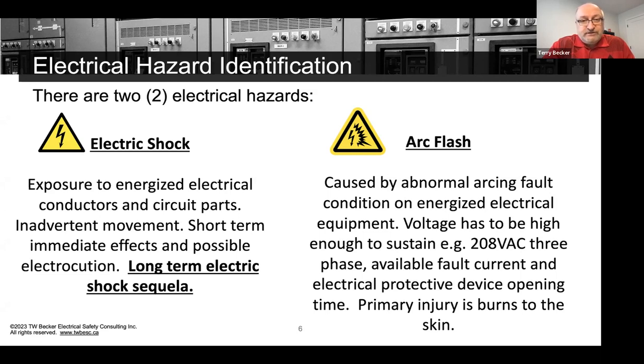The arc flash hazard, lots of stuff out there on arc flash, and I'm telling you, it continues to evolve in its growing personality. So I'm going to try and make some comments today to distill some of the misinterpretation of when a worker is exposed to arc flash. Again, it's voltage dependent, so that's really important that if we have a worker that is doing energized electrical work tasks, it's what the work task description is and what's the maximum nominal voltage of that electrical equipment, so that we can determine if we can sustain an abnormal arcing fault that becomes an arc flash. After that, we need to have some information about available fault current and that the worker is working under an electrical protective device that would see the abnormal arcing fault and open to minimize the incident energy or the heat that's released from an arc flash. So we'll go through that.